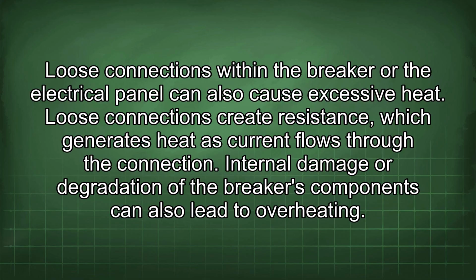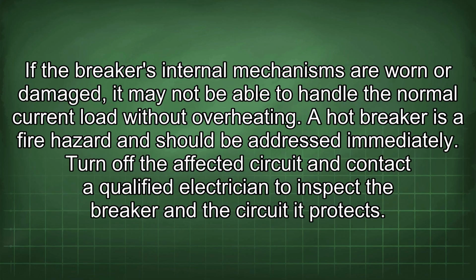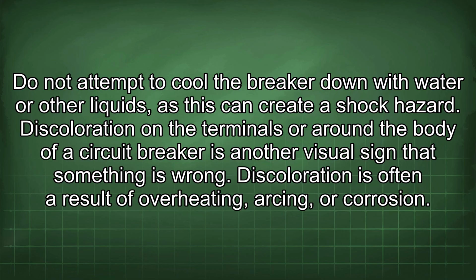Internal damage or degradation of the breaker's components can also lead to overheating. If the breaker's internal mechanisms are worn or damaged, it may not be able to handle the normal current load without overheating. A hot breaker is a fire hazard and should be addressed immediately. Turn off the affected circuit and contact a qualified electrician to inspect the breaker and the circuit it protects. Do not attempt to cool the breaker down with water or other liquids, as this can create a shock hazard.